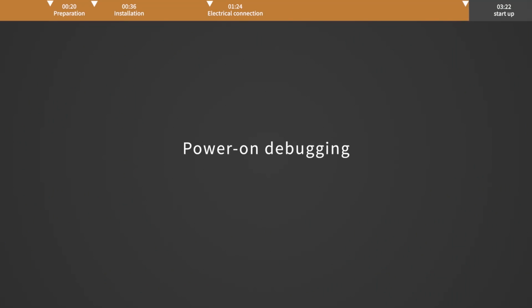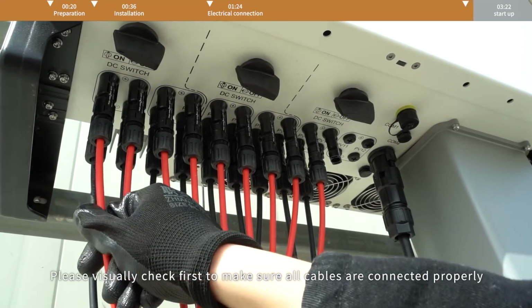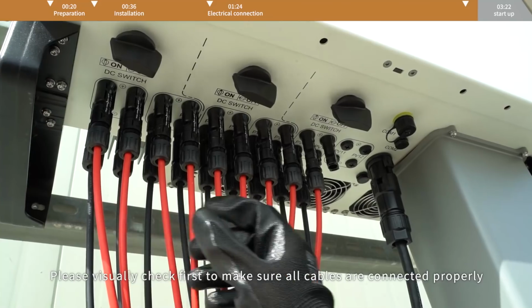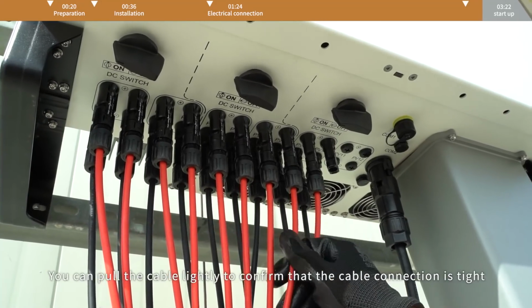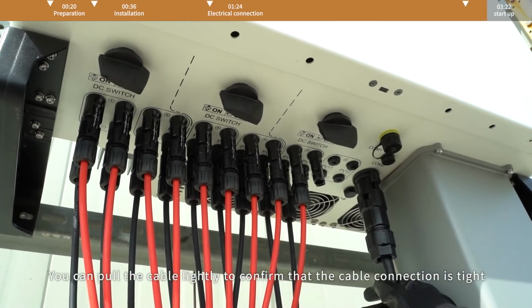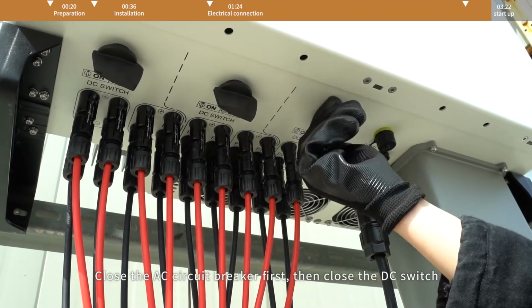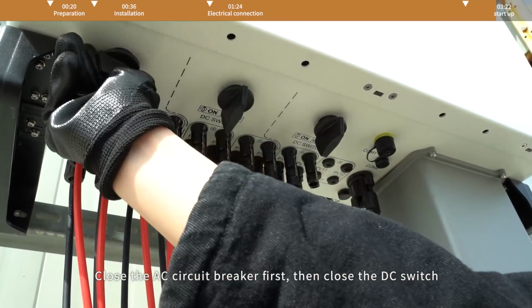Power on debugging. Please visually check first to make sure all cables are connected properly. You can pull the cable lightly to confirm that the cable connection is tight. Close the AC circuit breaker first, then close the DC switch.